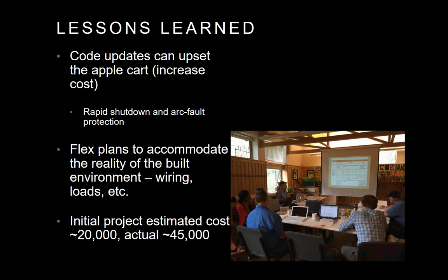A couple of things we learned going through this project: we ran into code updates that required additional safety features we hadn't anticipated, which ended up increasing the cost. Those were the rapid shutdown and the arc fault protection requirements. In fact, the reason the battery isn't running at the moment is that we're still waiting for a unit with combined rapid shutdown and arc fault protection, one of the first ever made, to pair with it.